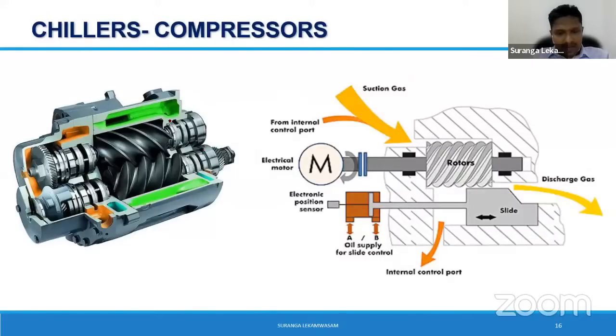Then you need to understand how we load and unload these chillers, because your cooling load varies. Accordingly, you need to load and unload your chiller. The best way is to load and unload the chiller by varying its speed. That's obvious, right? You can install a VFD with your motor, which drives your compressor at variable speed. So without any issue, you can load and unload your compressor. But these are big machines, right? Sometimes your motor capacity exceeds 100 kilowatt.